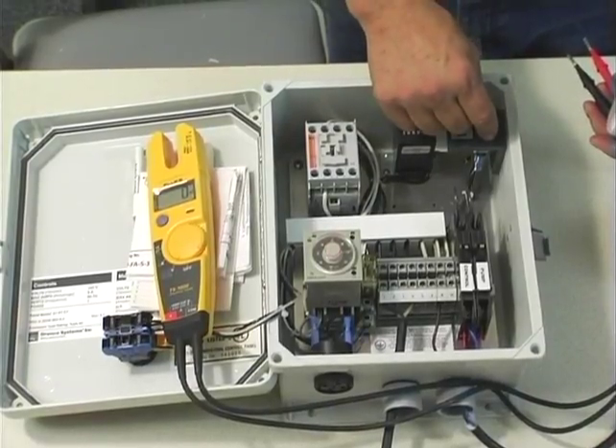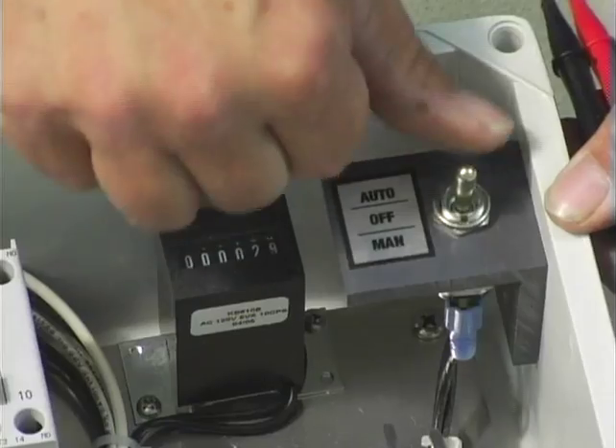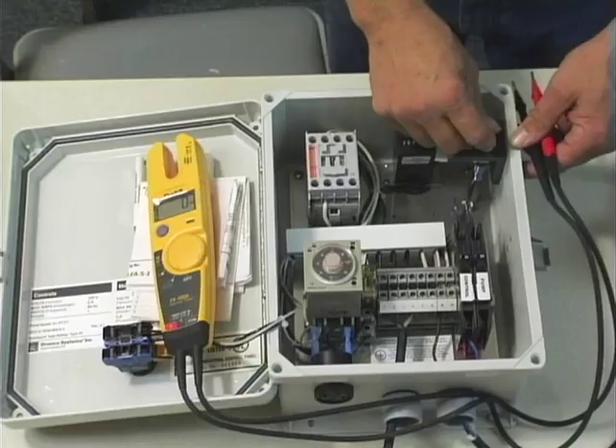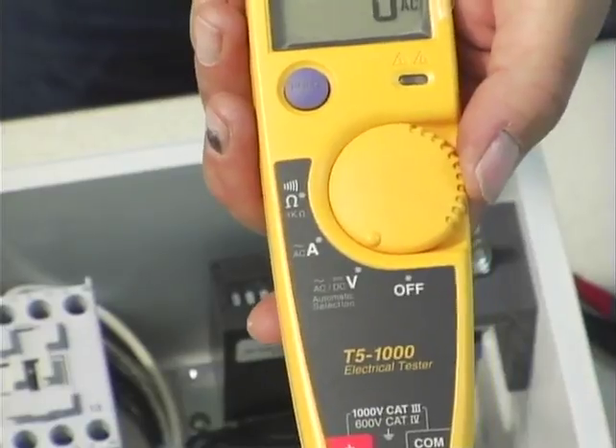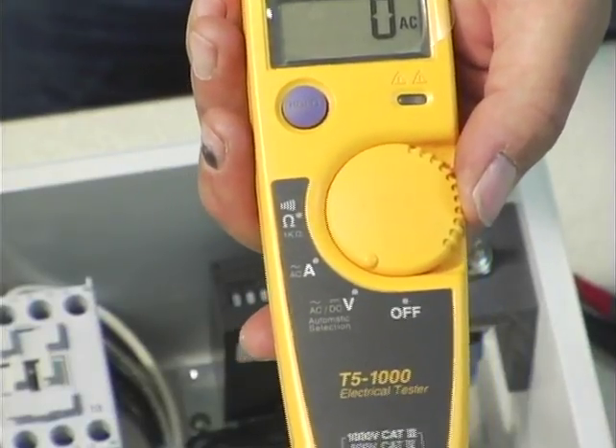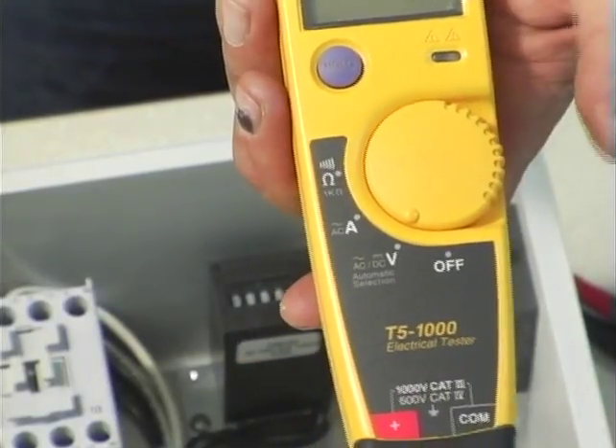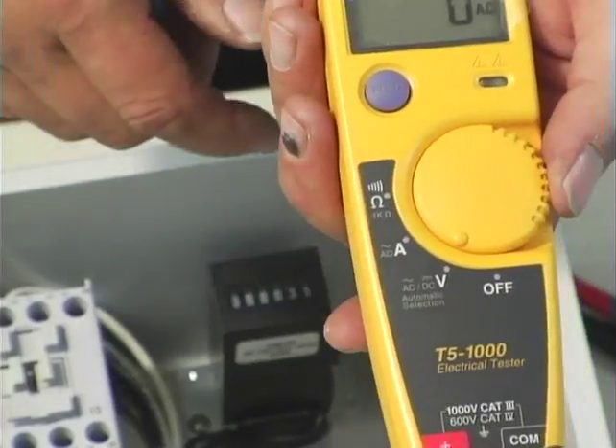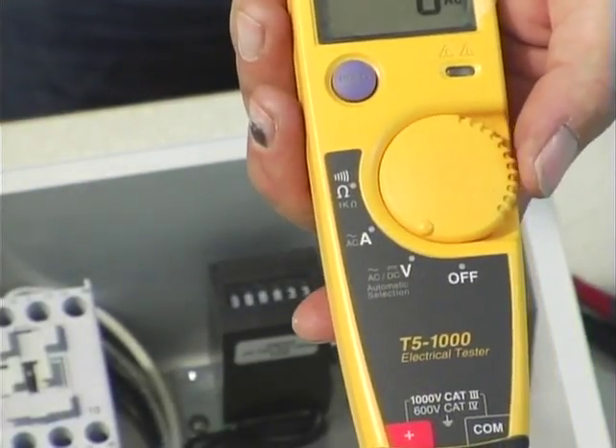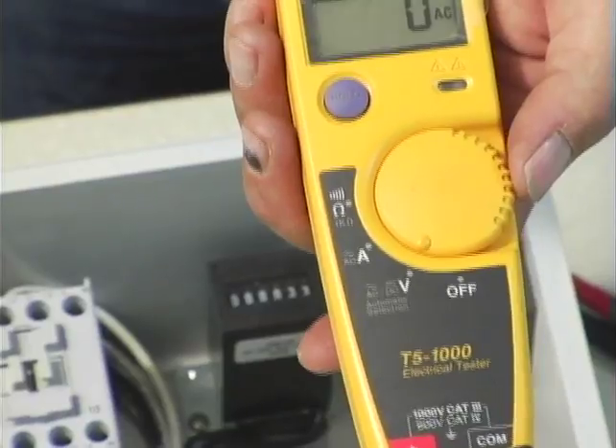So now we've replaced that. We take our switch and we go to manual, and now our motor contactor works again. We've determined that we had a faulty switch on the manual off auto. That was the first problem with this control panel. The second problem is we don't get a timer light when the float switch is activated, so what we're going to do is test our float.